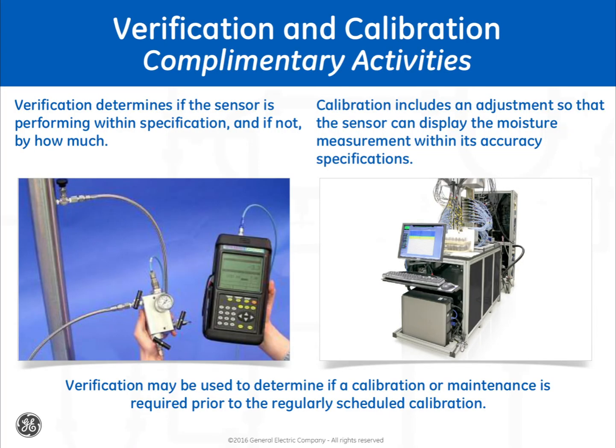Before diving into the technologies, let's talk about verification, the complement to calibration. It is important to note there are differences between verification and calibration. Verification is intended to determine if the sensor is performing within specification, and if not, by how much. Calibration includes an adjustment so that the sensor can display the moisture measurement within its accuracy specifications. These are two complementary activities. Verification may be used to determine if a calibration or maintenance is required prior to the regularly scheduled calibration.